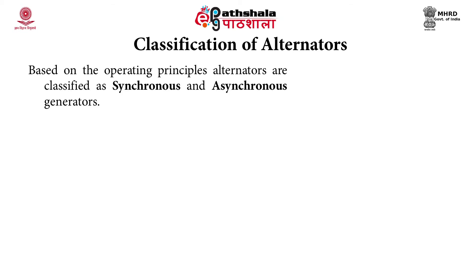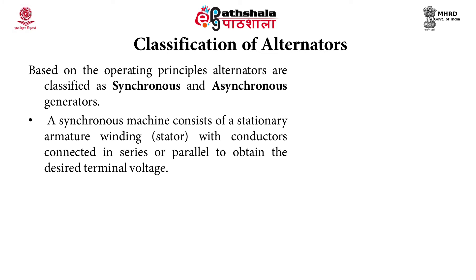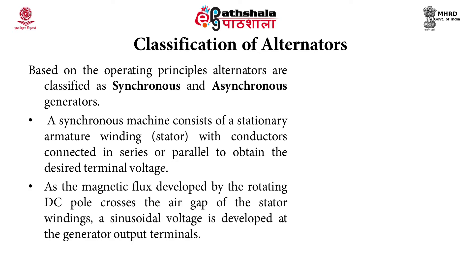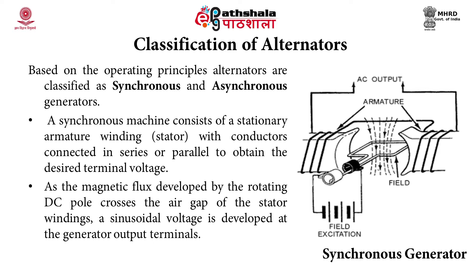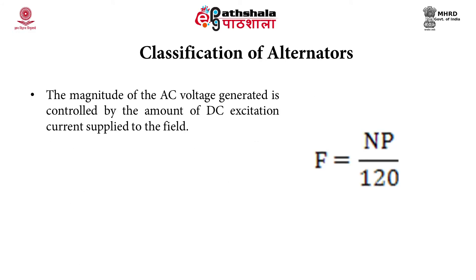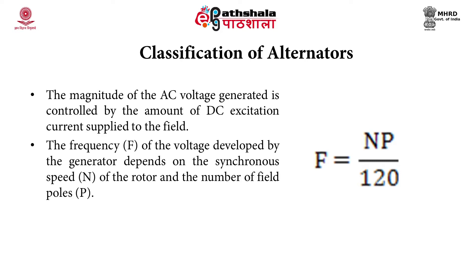Based on operating principles, alternators are classified as synchronous and asynchronous generators. A synchronous machine consists of a stationary armature winding on the stator, with conductors connected in series or parallel to obtain the desired terminal voltage. As the magnetic flux developed by the rotating DC pole crosses the air gap of the stator windings, a sinusoidal voltage is developed at the output terminals through electromagnetic induction. The magnitude of AC voltage is controlled by the DC excitation current, and the frequency F equals NP divided by 120, where N is synchronous speed and P is the number of field poles.